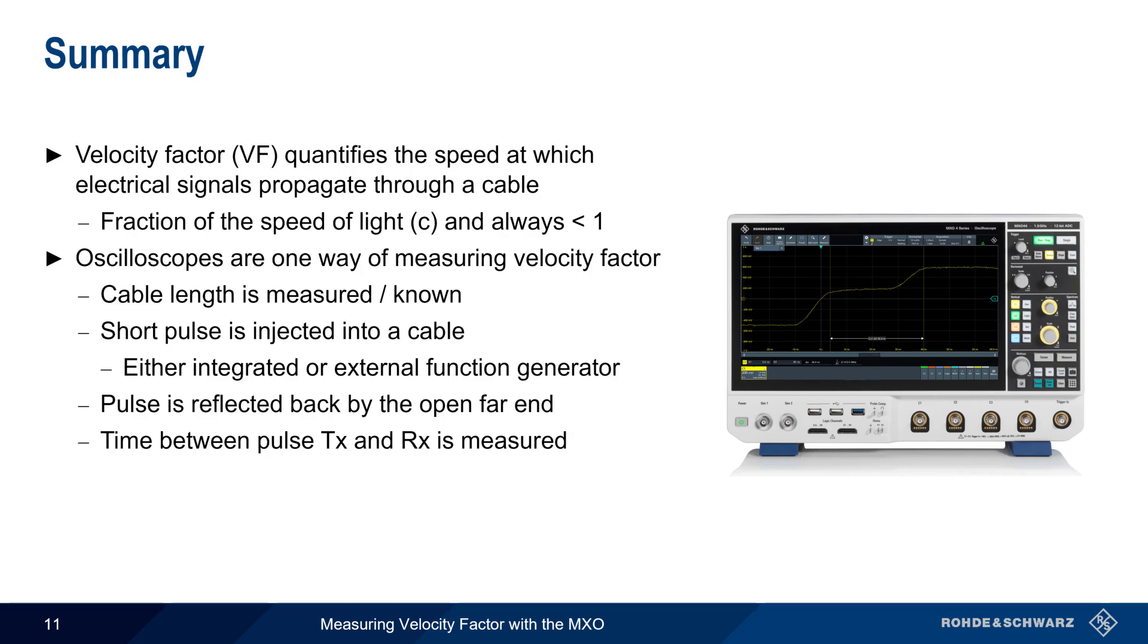The one-way delay, or half of this value, and a simple formula are then used to compute velocity factor. Although this procedure is very straightforward, correctly setting measurement parameters, such as the time base and trigger, are important in obtaining accurate and repeatable results.